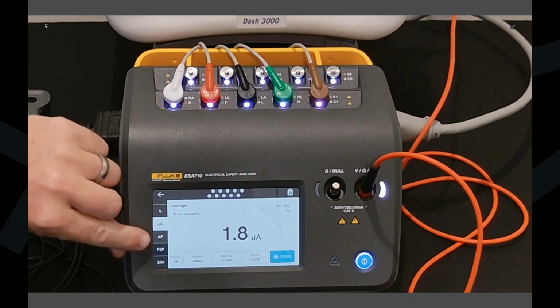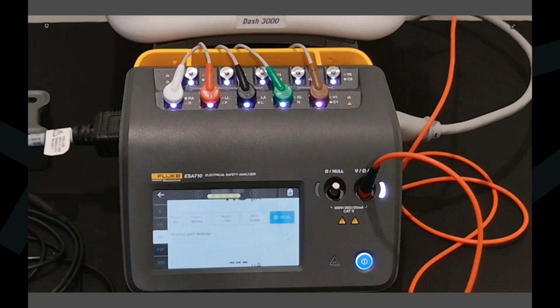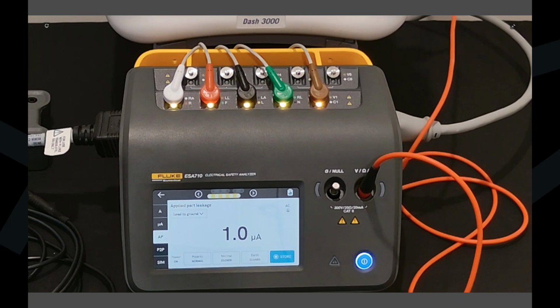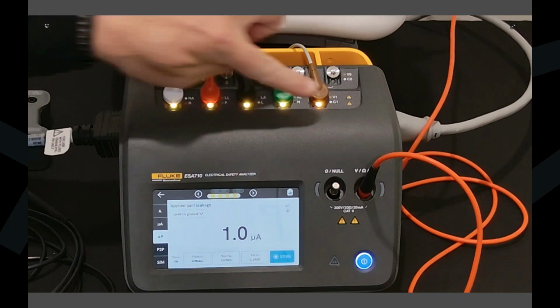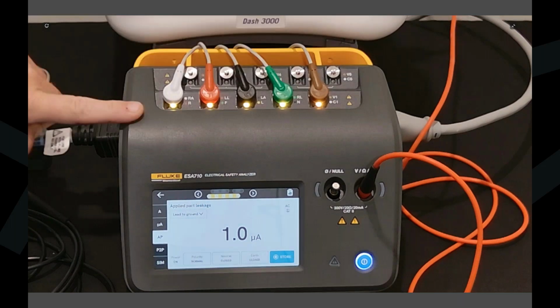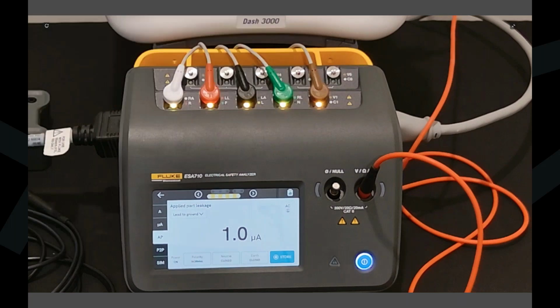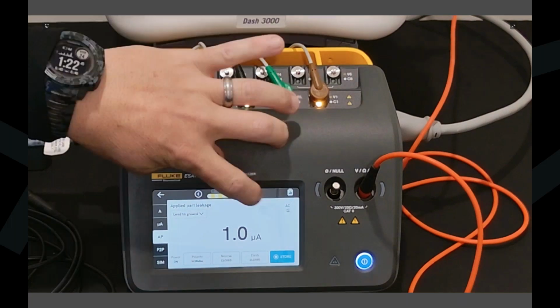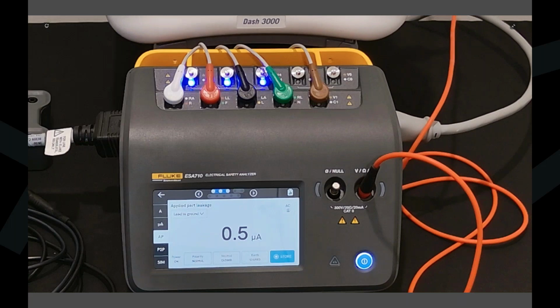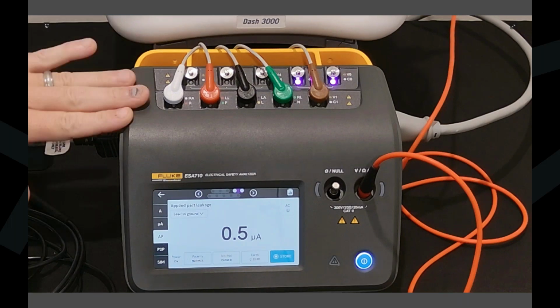Here's your applied parts testing. One of the differences between our 700 series and our 600 series - our 600 series only had 5 applied parts at the top without LED indication. Here you have LED indication letting you know the groupings, and you have 3 different groupings. So if you wanted to do 3 parts, there's a grouping, and there's another grouping. If you had a defibrillator with ECG applied parts testing and you wanted to do your hands-free paddle testing, you could do it there, and if you had something else, you could do it on your other 3 groupings and set that all up. In manual mode, you can set it up however you wanted to do your applied parts testing.